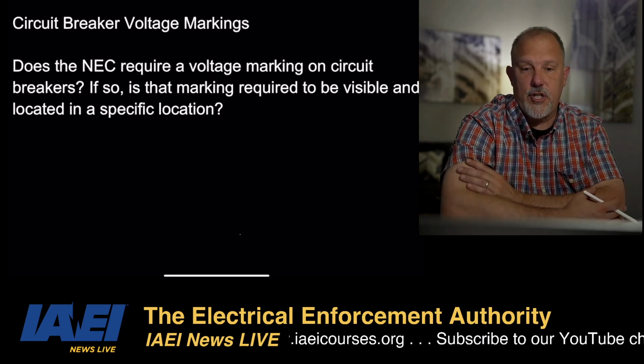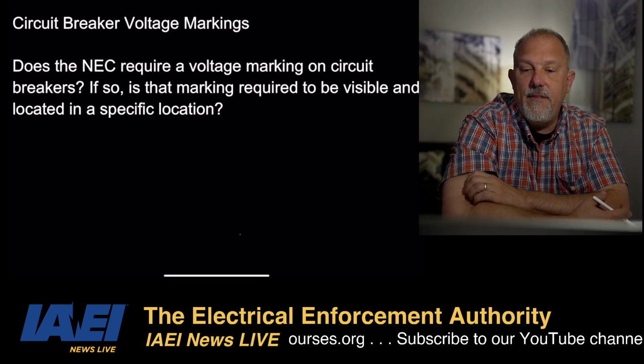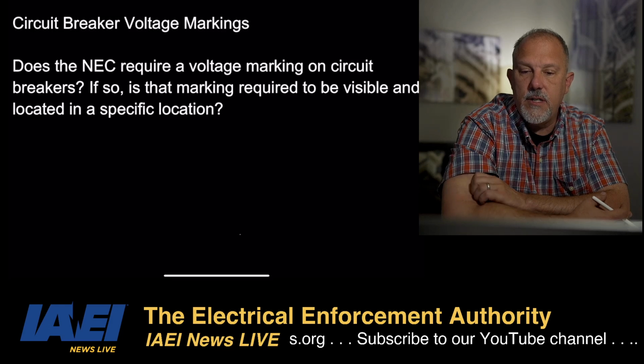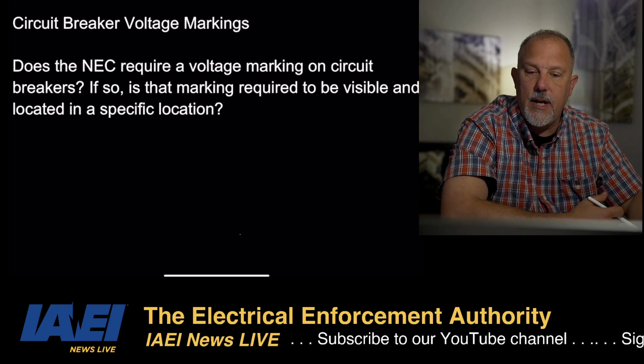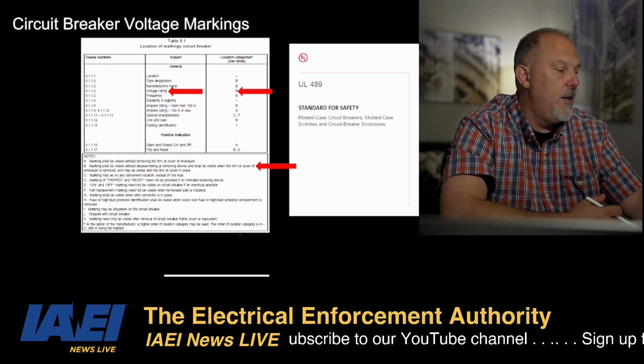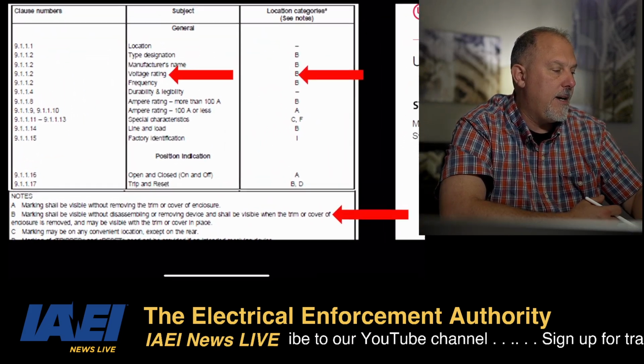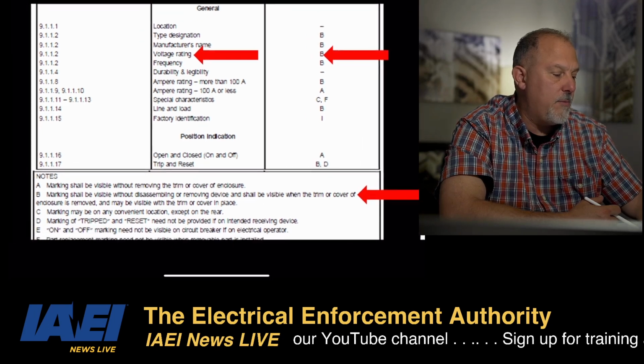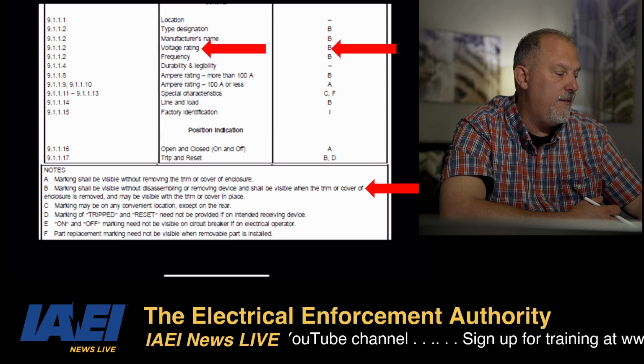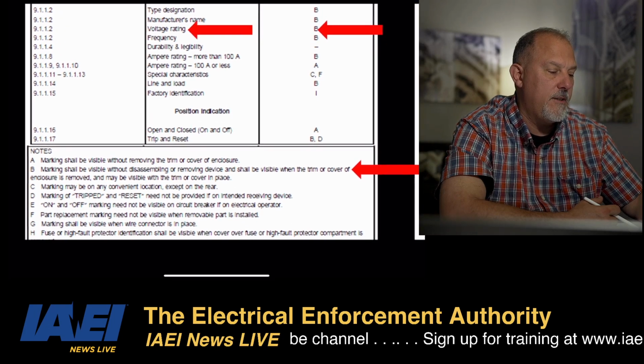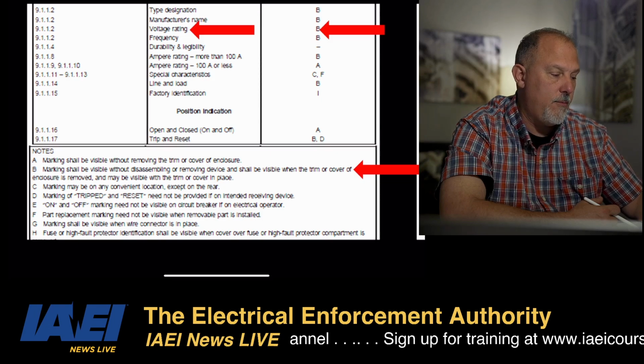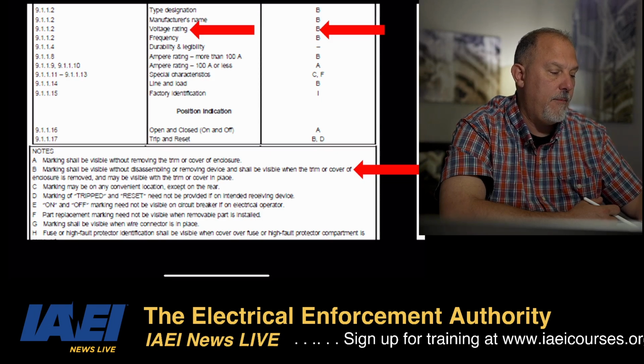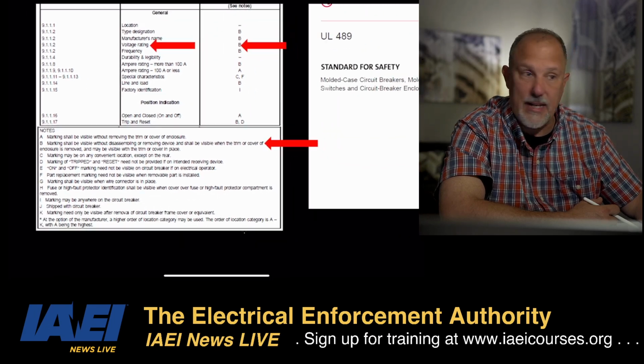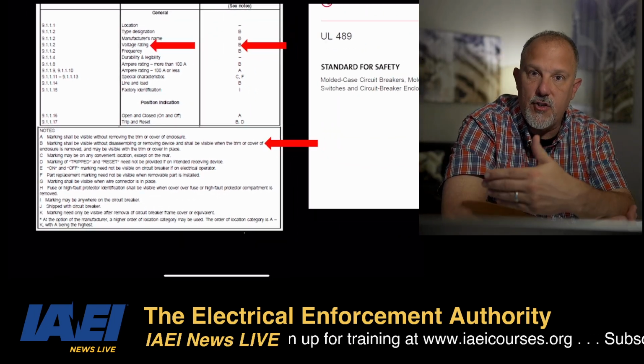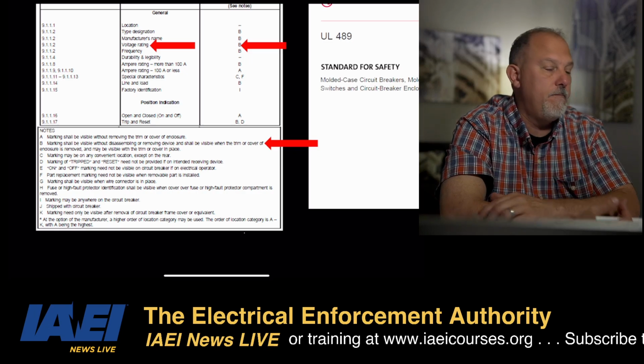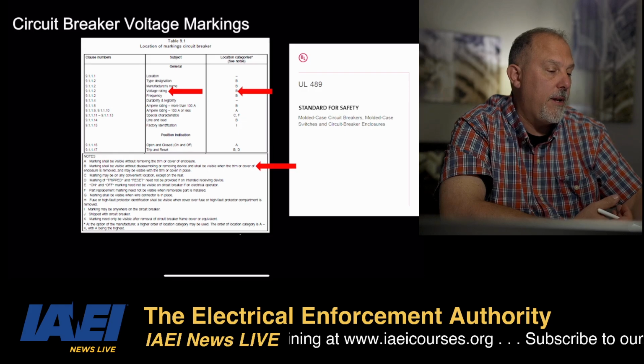Here's the next question. Does the NEC require a voltage marking on circuit breakers? If so, is that marking required to be visible and located in a specific location? There's your voltage. Remember, in 489, voltage has to be location B, which means the marking shall be visible without disassembling or removing the device. It shall be visible when the trim or cover or enclosure is removed and may be visible with the trim or cover in place. So I may have to remove that trim cover to see the voltage rating. And that's per UL 489.